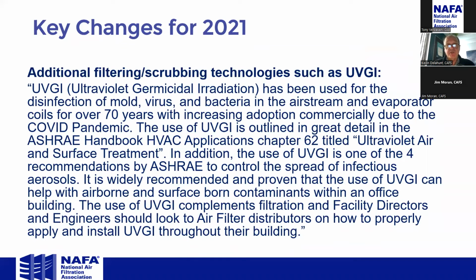Key changes again for 2021 was looking at UVGI, ultraviolet germicidal radiation, which has been used for the disinfection of mold, virus, and bacteria for over 70 years. And it obviously really came to the forefront again during the pandemic. So to design and operate this, you need to bring somebody in that has a specialty in it and understands it and is able to place the units in the correct position and get you the correct amount of units that you need to provide the treatment that you need. Use of UVGI complements filtration. It doesn't replace it. It does one job, and the mechanical filters do another job.